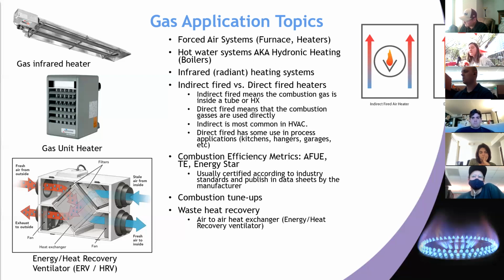We will also work probably a lot with waste heat recovery. It's really hard to give a recommendation for waste heat recovery from a process system because those are almost all custom and unique. You might have 500-degree heat available from a furnace or a foundry somewhere. And the challenge is finding a match between the availability of the heat and a demand for it somewhere else.